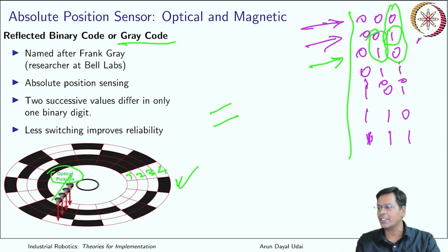So if by any fault you see 2 wires changing, that means your device is faulty. It has fault tracing capability within the device itself. You should not see 2 wires changing at a time. If it is changing, your device is faulty.